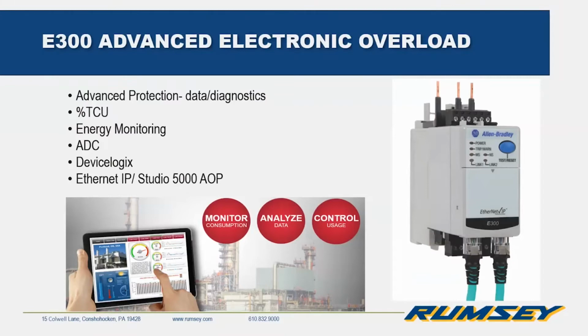Another feature is ADC, which stands for Automatic Device Configuration. So you may be familiar with this in some of the other Allen Bradley products. They've been using this. This can be very powerful if this overload happens to fail at 2 o'clock in the morning on third shift. What this feature does, it takes all those parameters that you have programmed into it, it stores it on the controller in the PLC. So if it were to fault out or go bad, it can be replaced, put a new overload in, and then the controller will recognize that and push out all the parameters to the new overload, and you're up and running again. So that can be very helpful.